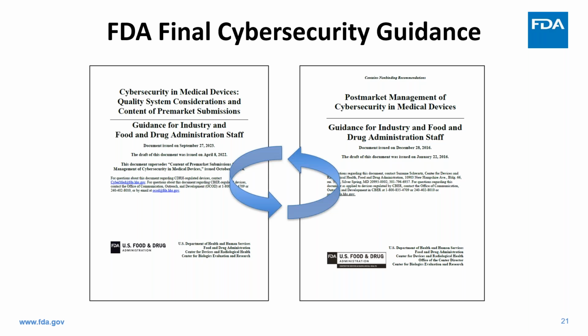And I can give just a really quick example of what I mean. We had a circumstance, and I'll give a little bit more detail later, where certain medical devices became unavailable during a cyber incident because the design required them to communicate to a remote cloud in order to calculate dose, how much of a given treatment to give a patient. When that cloud connection was interrupted, the devices essentially weren't able to function. So I can tell you that we added questions into the review, essentially saying, do you have a 100% dependency on a remote capability? And if that remote capability goes away, what is your backup plan? Do you have one? And if the answer is there is no backup plan, there may be a chance that device is not getting approved with that design. So we do this in a lot of cases. We take things from the post-market, we update our review criteria in the pre-market, and it becomes, we hope, a very virtuous cycle. So next slide.